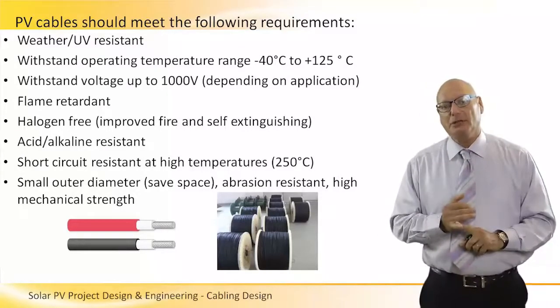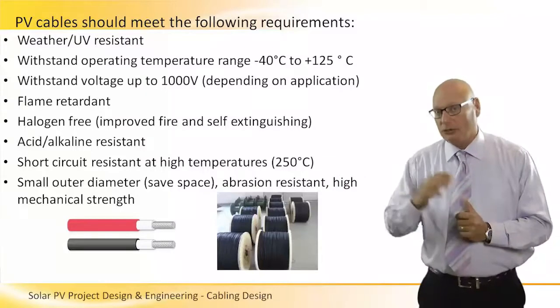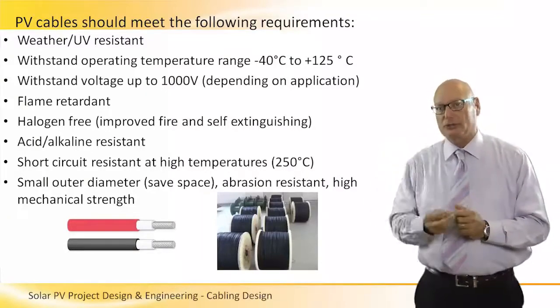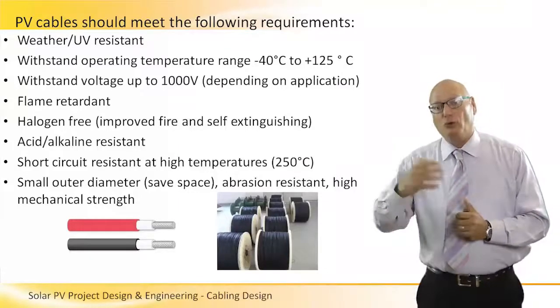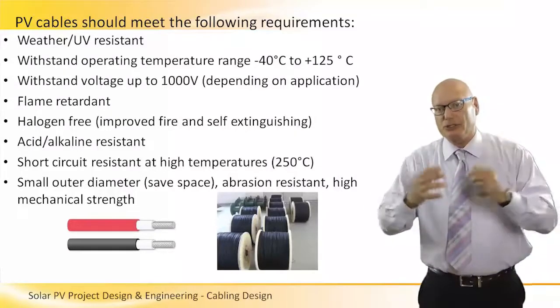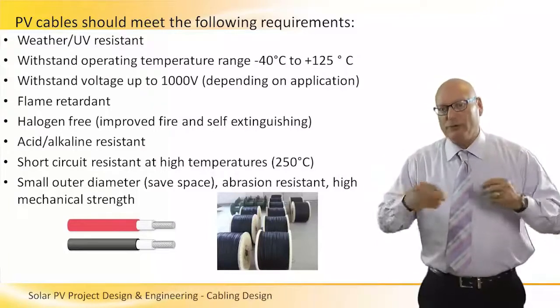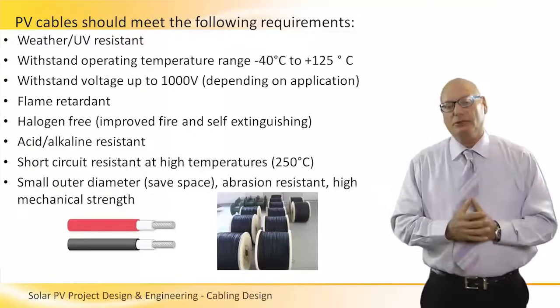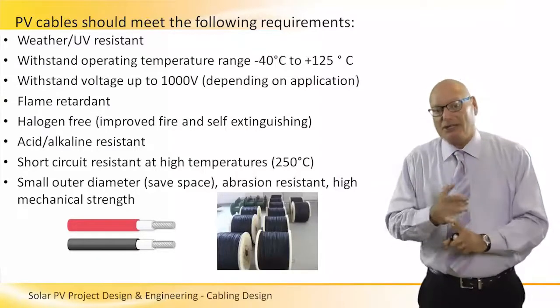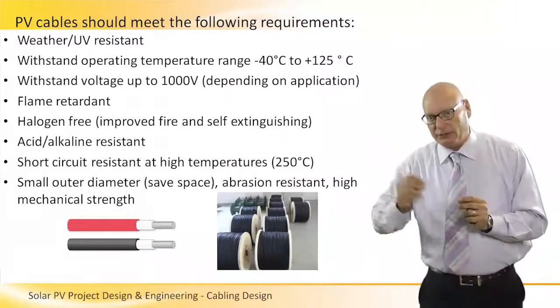In order to minimize this loss, we have to have a weather UV-resistant cable. The cable should withstand operating temperatures of minus 40 to plus 125 degrees C. We'll see later the effect of temperature on the voltage drop of the cables. Up to 1000 V depending on application. Flame retardant, halogen free to improve fire safety and self-extinguishing.